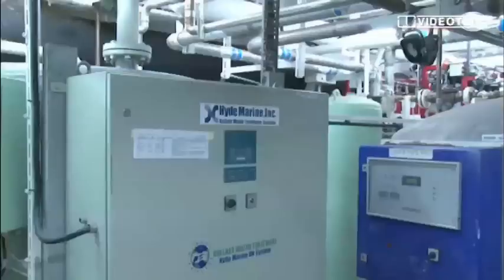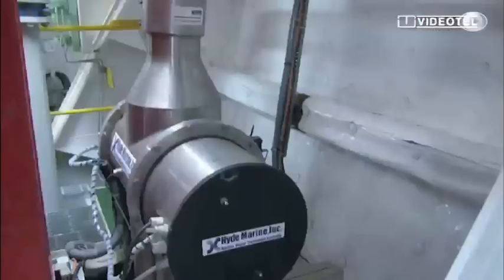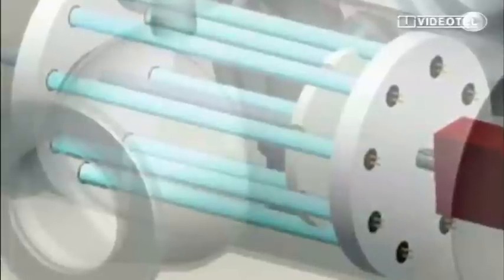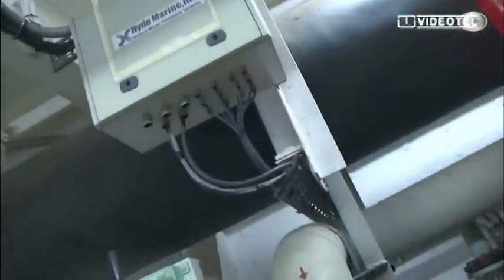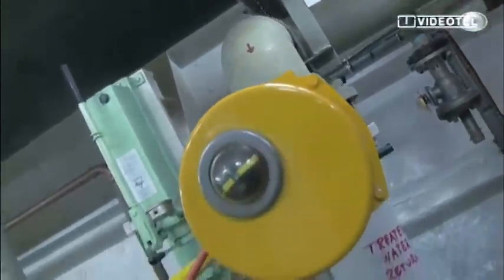The UV system ensures a consistent UV dosage. On the main line we have a flow meter which allows us to monitor the flow rate of the water. According to different changes in the balance of the water, this system reacts as well, changing the intensity of the UV radiation if necessary — usually it's around 90%. Just before delivery overboard, we treat the water again to make sure that all microorganisms have been killed, and we send back seawater in a clean environment.